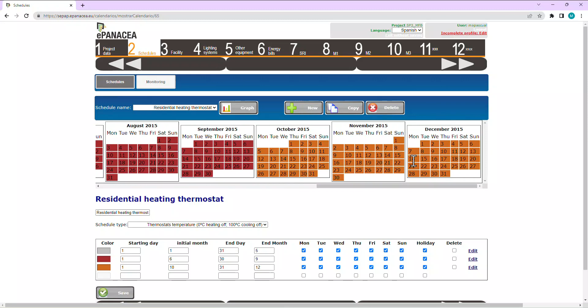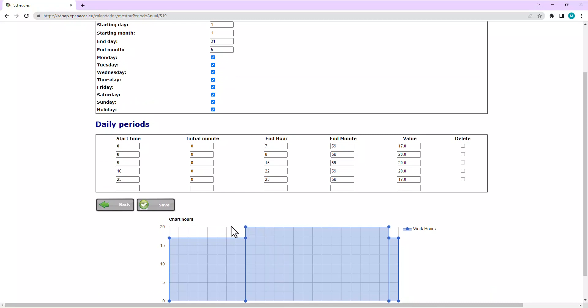How is, for example, a gray day defined? It's defined in this row. Gray days start from the 1st of January to the 31st of May. They apply to all the days in the week. And if we want to see how these are defined, I click Edit. Here we can see that the heating thermostat schedule is defined having 17 degrees during the first hours of the day, during the night.